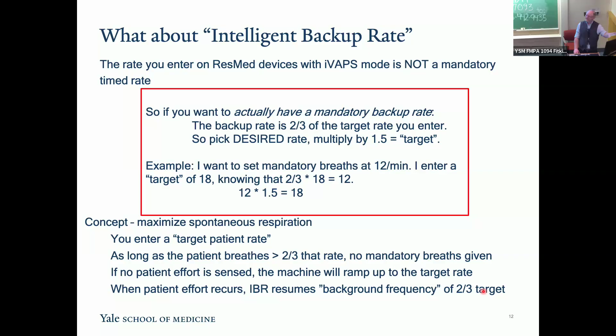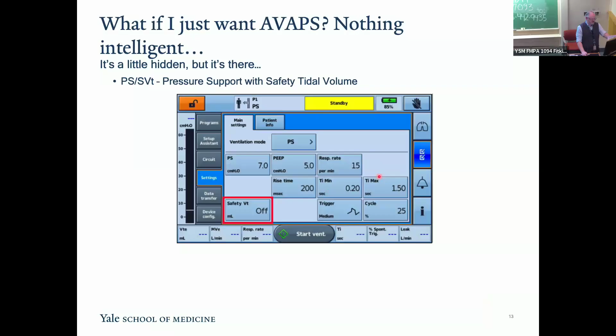So what if I just want good old AVAPS? I don't want anything intelligent. Thank you, ResMed. So actually it exists. AVAPS as a mode exists, but it's hidden. It's not called AVAPS. It's called pressure support with safety tidal volume. And the way you find that, if you're in front of a ResMed Astral ventilator and you go into the screen setting the modes, you would hit the pressure support screen here. That takes you to the next screen, which allows you to set up all the settings here.